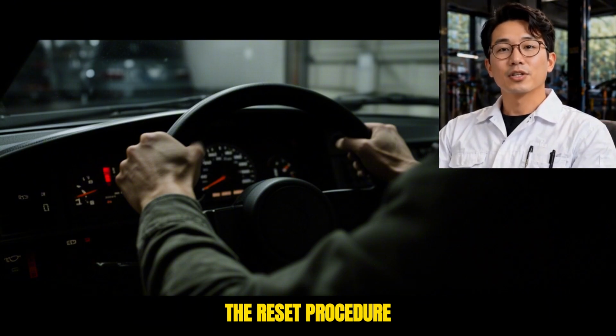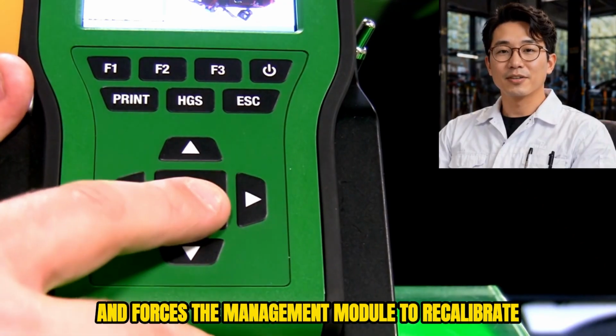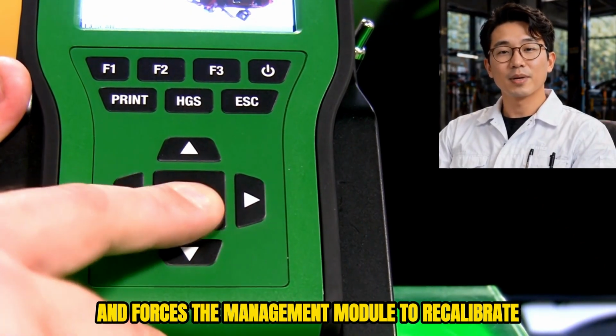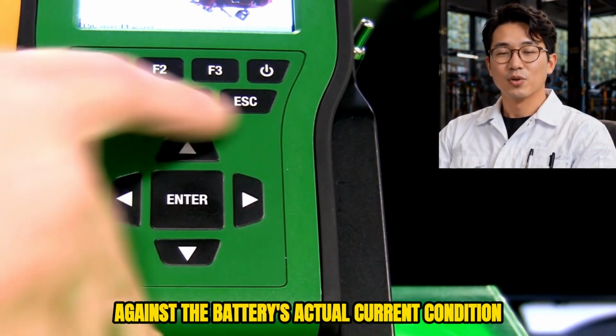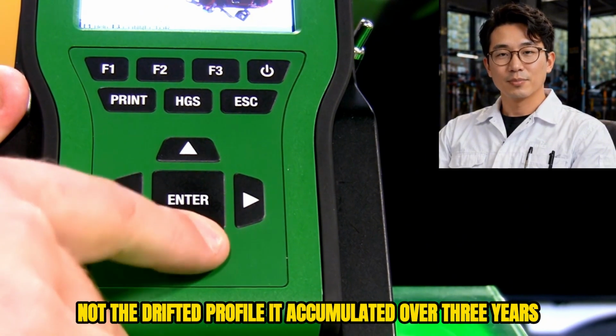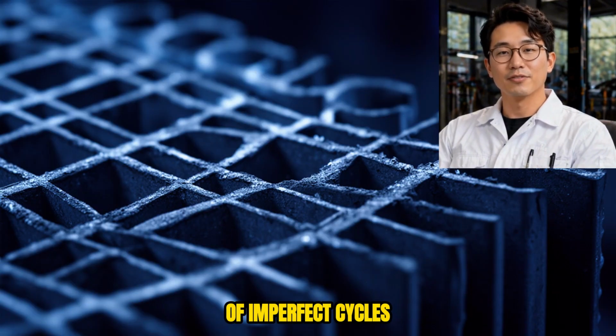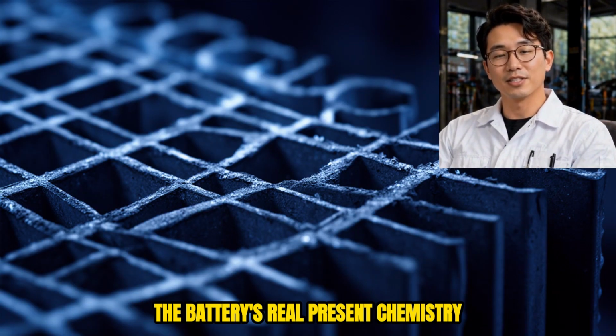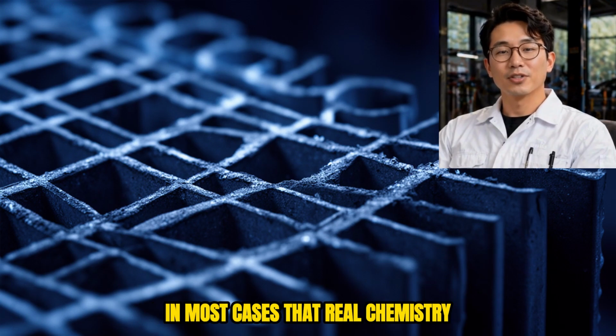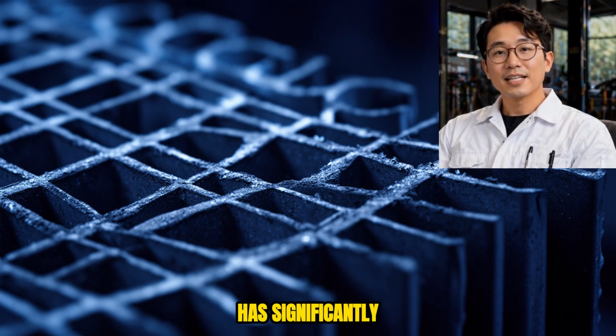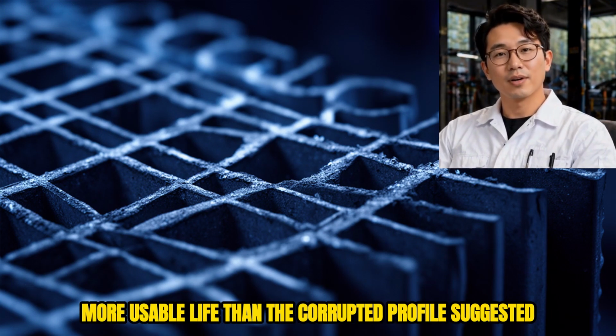The reset procedure clears those corrupted learned parameters and forces the management module to recalibrate from scratch against the battery's actual current condition, not the drifted profile it accumulated over 3 years of imperfect cycles, the battery's real present chemistry. In most cases, that real chemistry has significantly more usable life than the corrupted profile suggested.